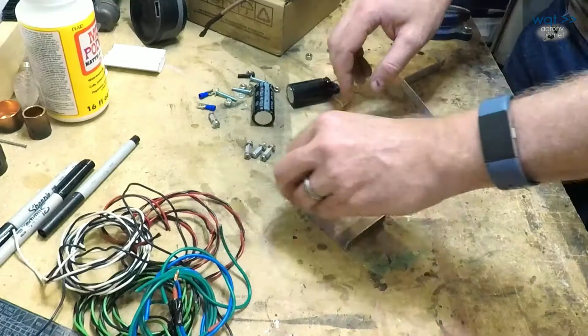So if you put a fuse on one of the secondary leads before you go into it, or if you're doing a center tap transformer, on both leads, that will help protect the transformer winding against a rectifier fault. Doesn't happen that often, but it can.